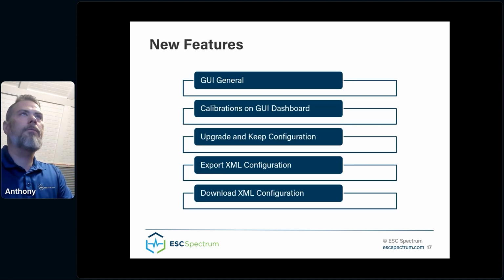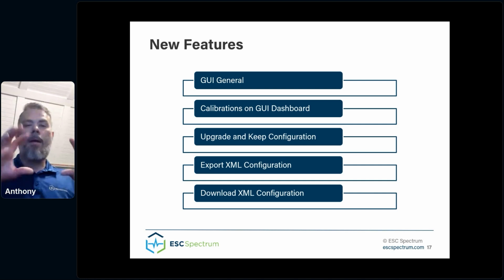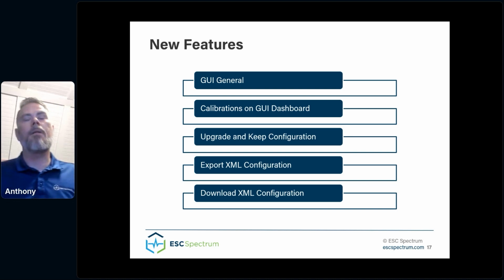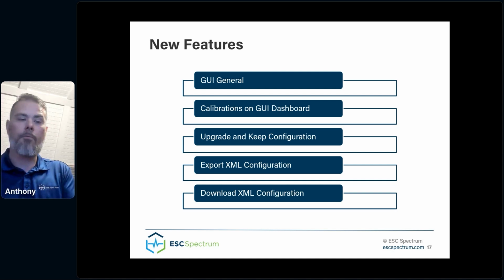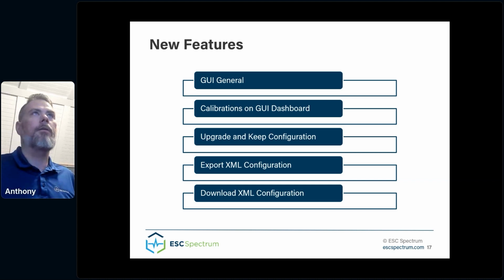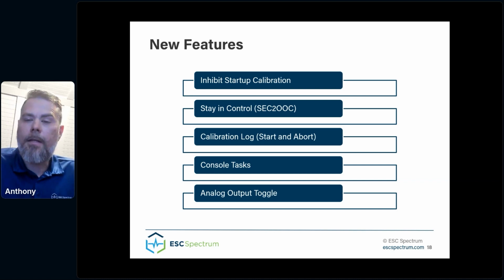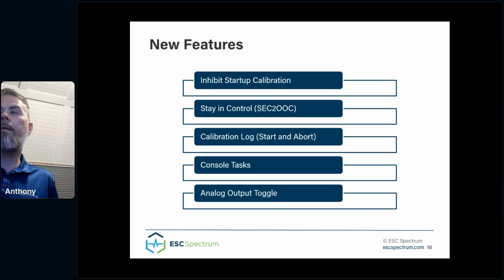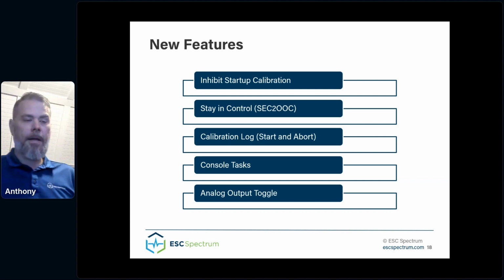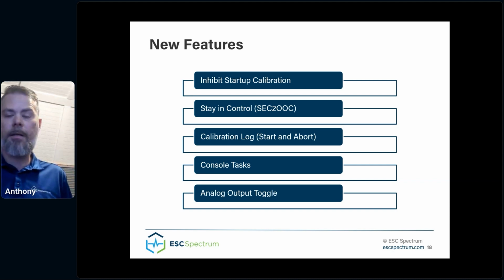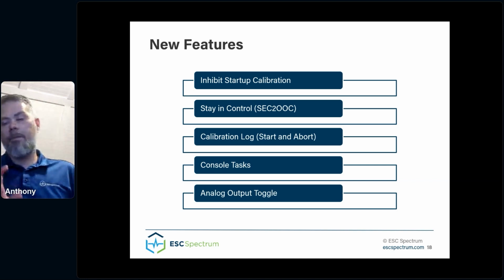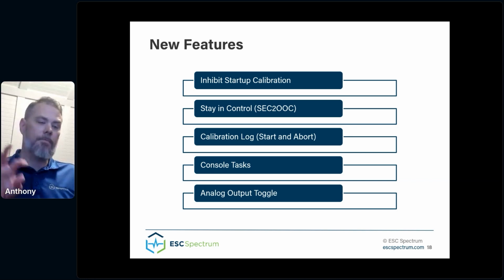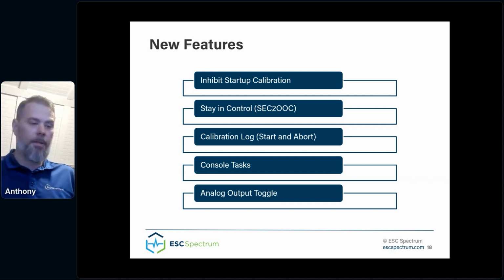Real quickly, here are the new features I'm going to cover. We made improvements to the front panel GUI, added calibrations to the GUI dashboard, and added the ability to upgrade your firmware while keeping your configuration. We added the ability to export your current configuration to an XML file, and then re-import that XML configuration so it becomes your configuration on your data controller. We added the ability to save on calibration gases by inhibiting startup calibrations. And we added the ability to help stay in control by simplifying the way math functions like sector OOC kick off automatic calibrations. Many people will have this configured already, maybe set up by an engineer for them. We've simplified it to reduce implementation time, and to give you the opportunity to implement it yourself if you don't already have it.